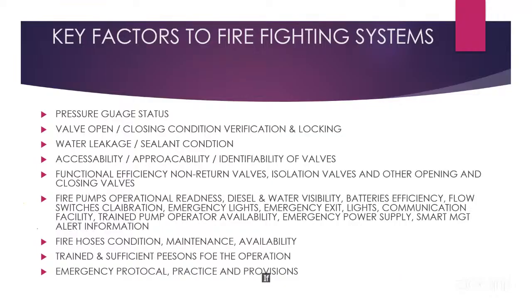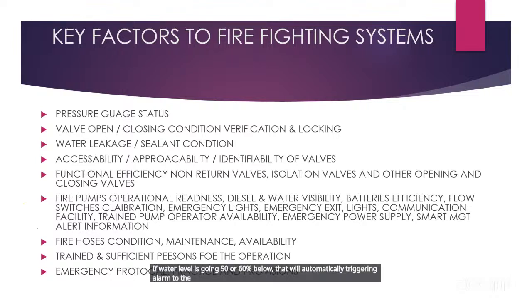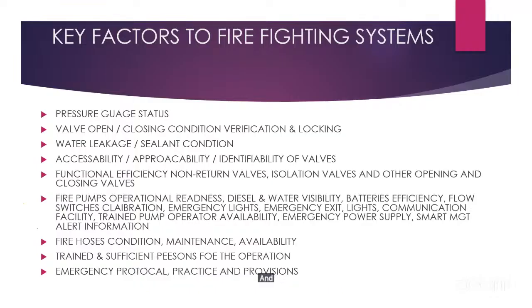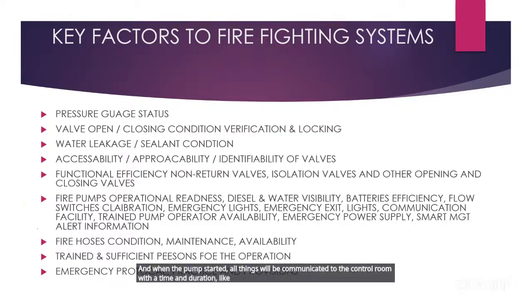If the water level goes 50 or 60% below, that will automatically trigger an alarm to the fire control room. Even in foreign countries, they are connected to the public fire services also. So there is a smart alarm system. When the diesel level goes below, the water level goes below, the normal power goes off, and when the pump starts, all things will be communicated to the control room with the time and duration. So this is a smart management information system that one should follow.